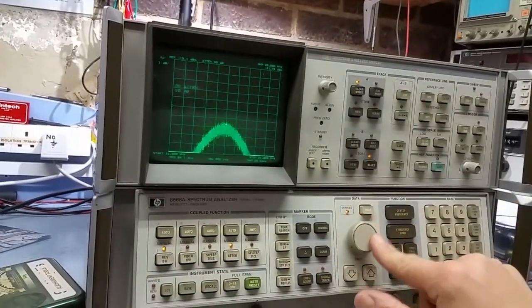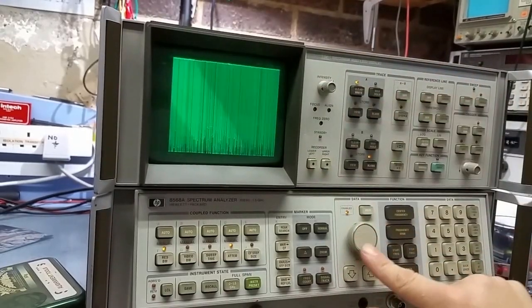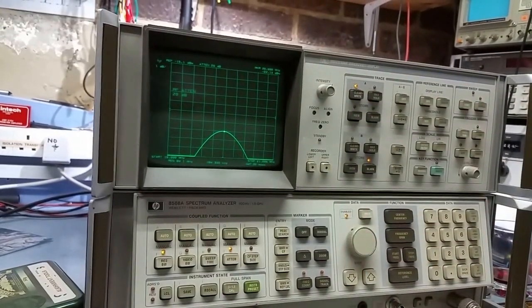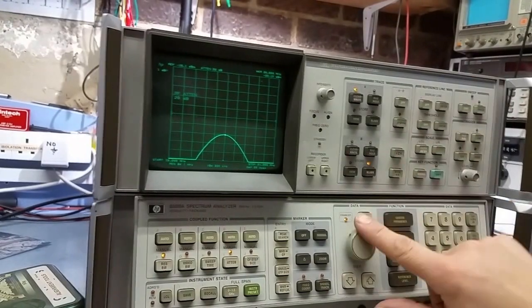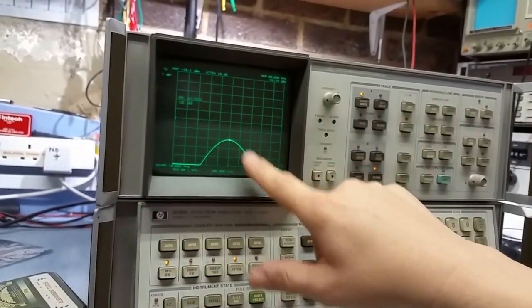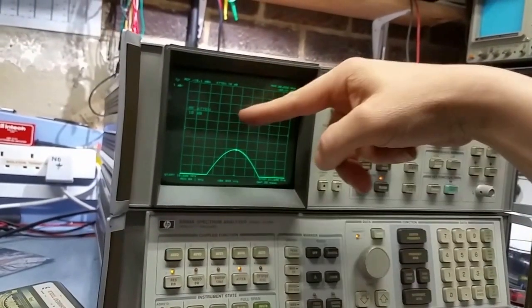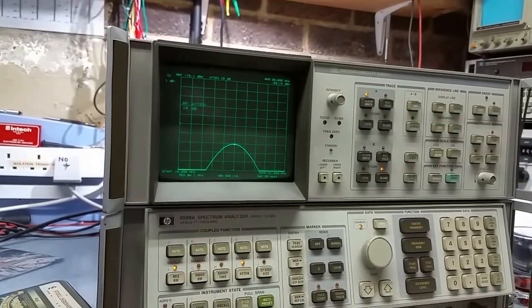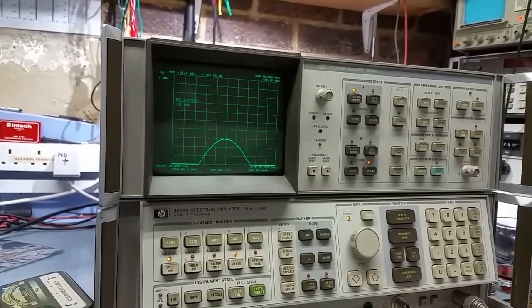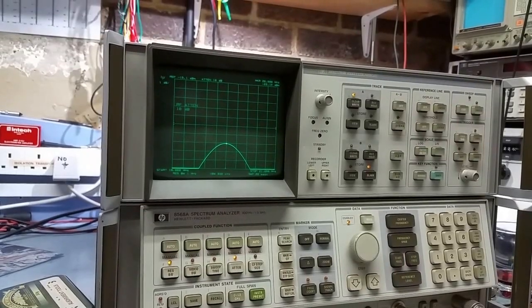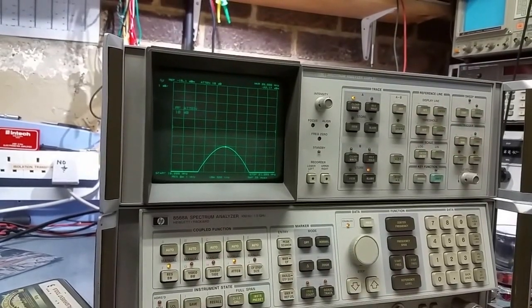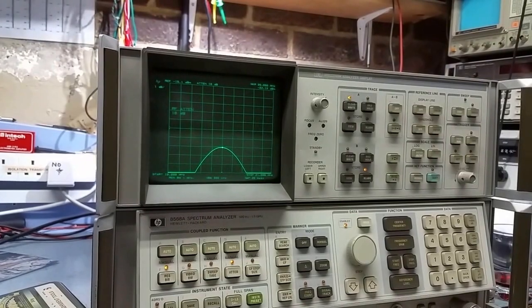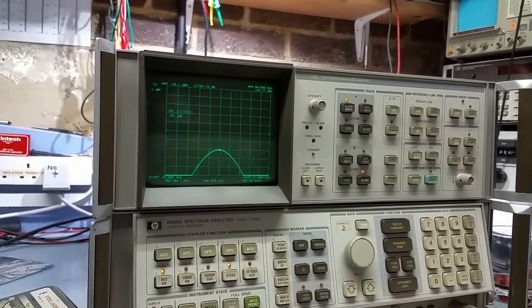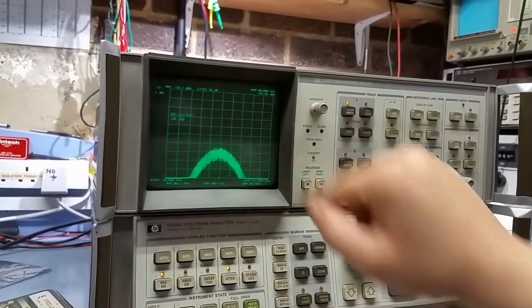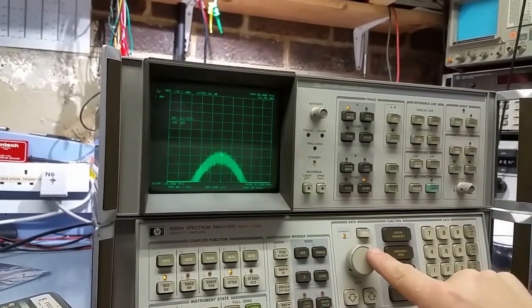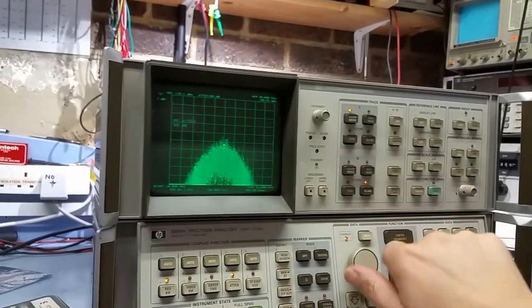The higher you go, you just get scatter on the screen. So you can see at the minimum attenuation, it's a clean signal, but it's far too low. It should be up here somewhere. So that's going to need looking at. As far as I can tell, everything else is okay. And I think one of the engineers, as I said, mentioned there was a high noise floor on it, and I think the high noise floor is all that crap you're seeing there. When you put a strong signal in, it kicks in the attenuator, and you get all this noise.